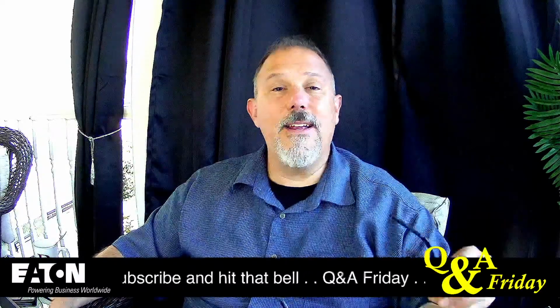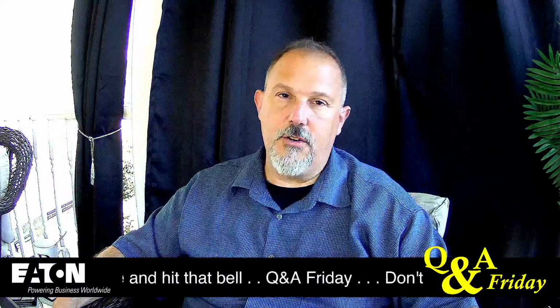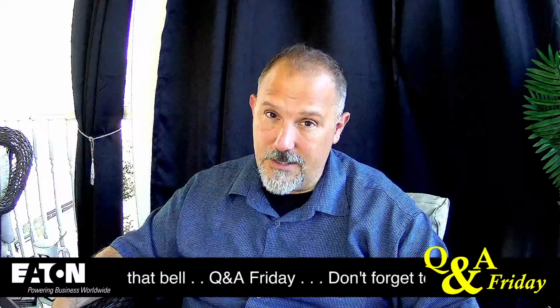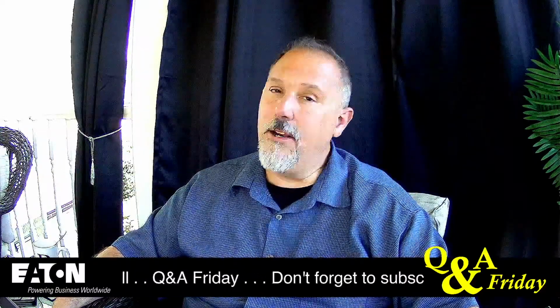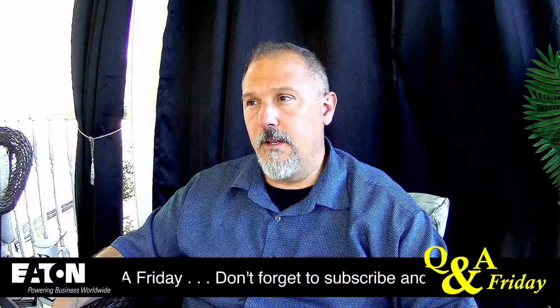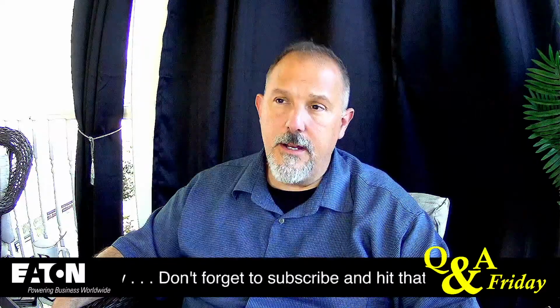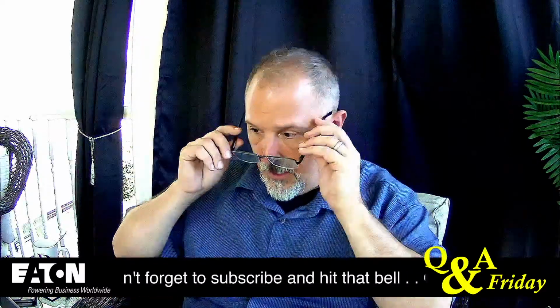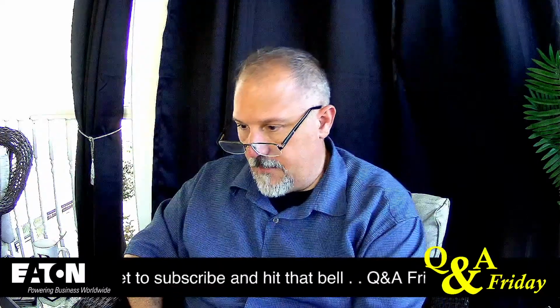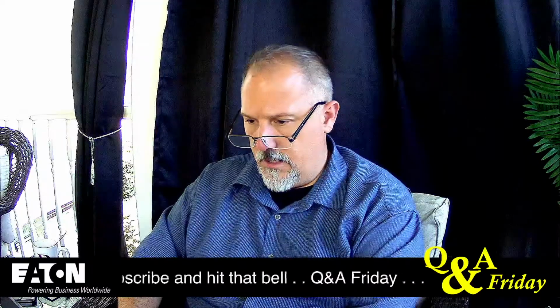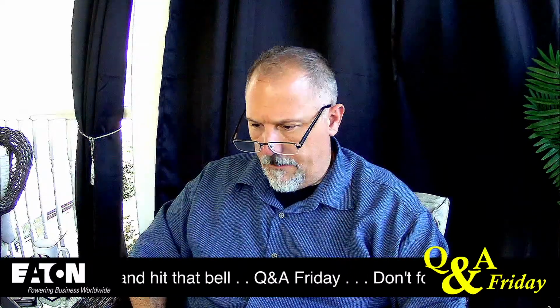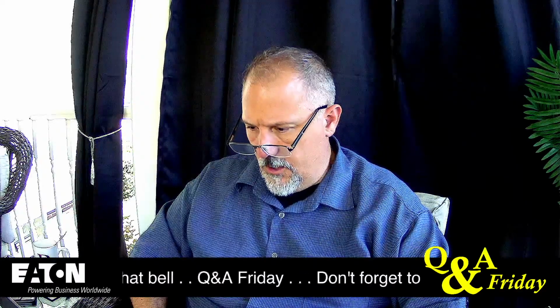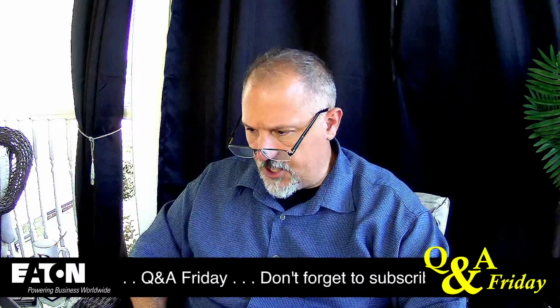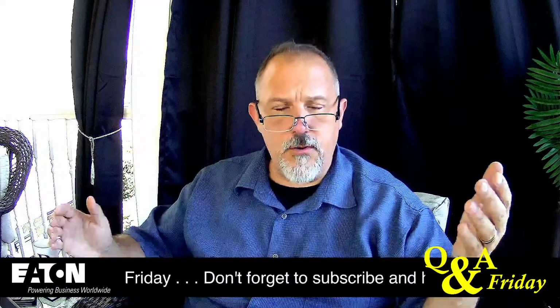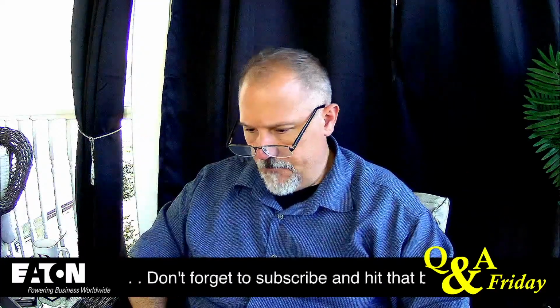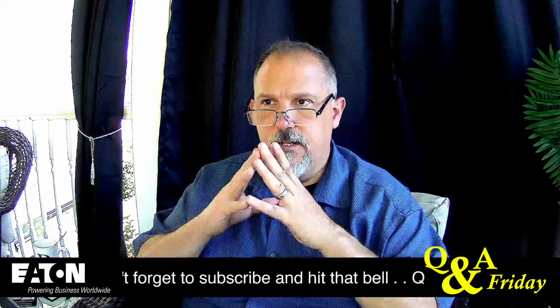If it's not listed that way, if it's not at least tested that way, the challenge that you run into is it's just an opinion. Think about it. You can say, I have a barrier. I don't know of any product. I know MCCs that are arc resistant. I know we have a motor control center that you can rack the breaker out of. Eaton MCC arc resistant. So we have arc resistant for increased arc flash protection. We have arc vault. We have the ability to rack the bucket out. But I don't know.